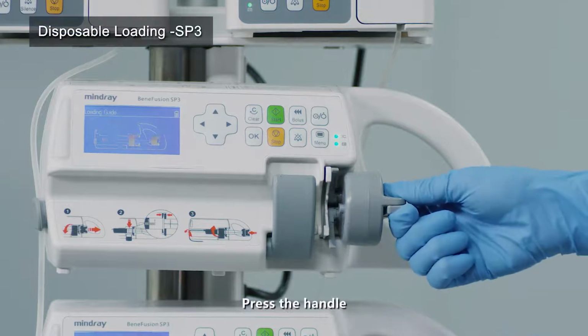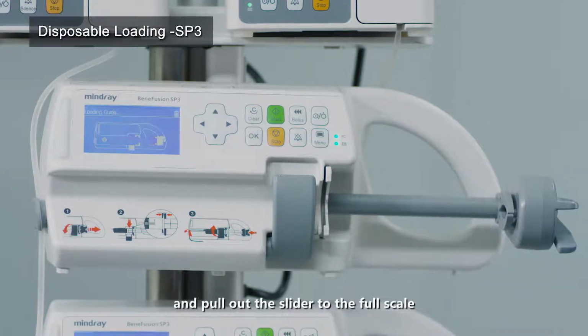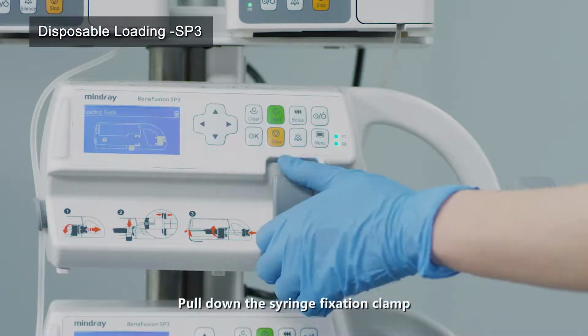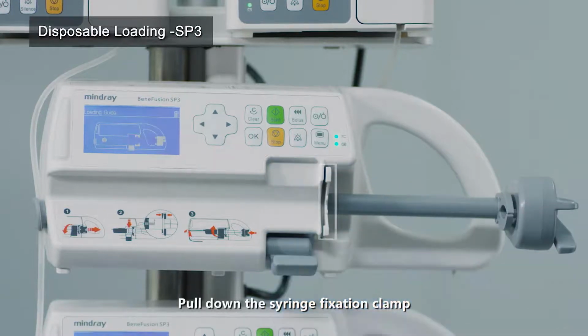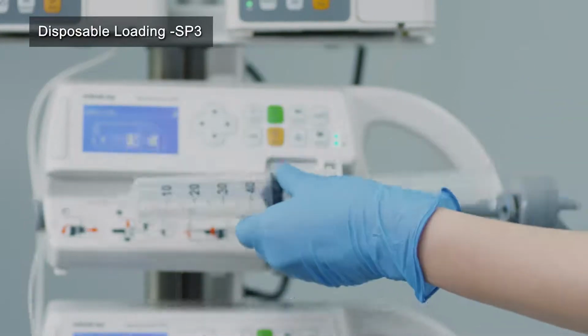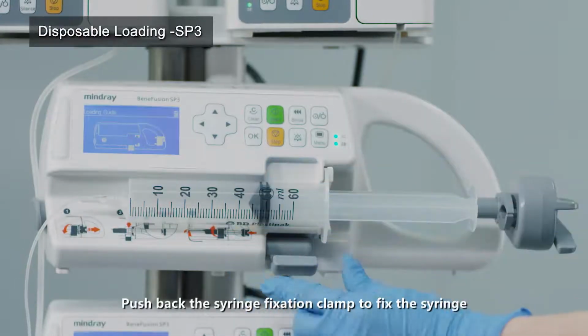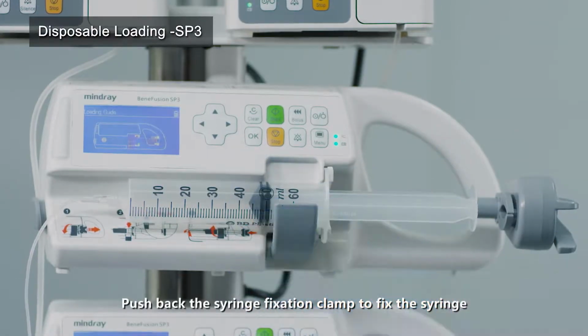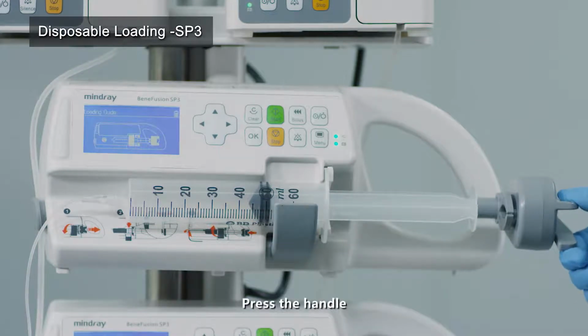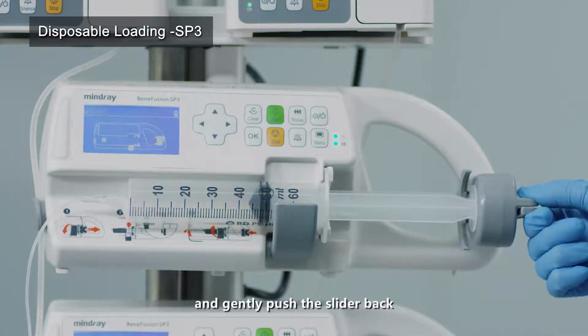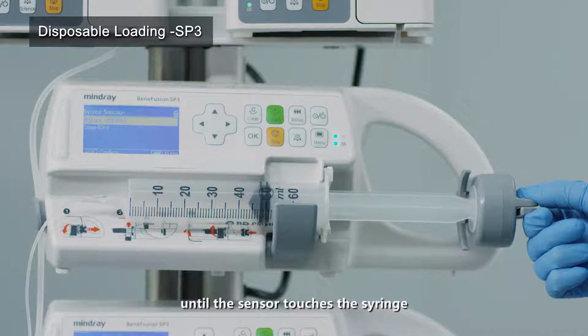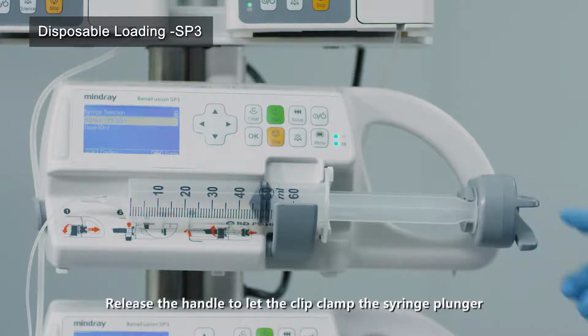Press the handle and pull out the slider to the full scale. Pull down the syringe fixation clamp. Insert the end of the syringe plunger into the gap. Push back the syringe fixation clamp to fix the syringe. Press the handle and gently push the slider back until the sensor touches the syringe. Release the handle to let the clip clamp the syringe plunger.